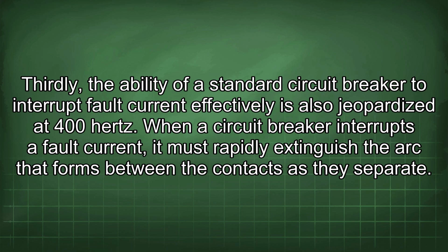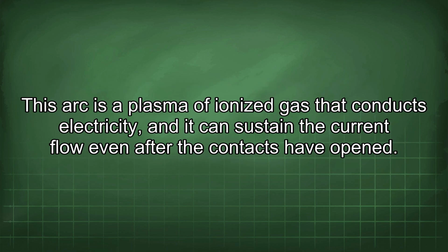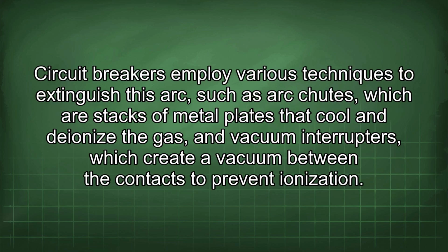When a circuit breaker interrupts a fault current, it must rapidly extinguish the arc that forms between the contacts as they separate. This arc is a plasma of ionized gas that conducts electricity, and it can sustain the current flow even after the contacts have opened. Circuit breakers employ various techniques to extinguish this arc, such as arc chutes, which are stacks of metal plates that cool and deionize the gas, and vacuum interrupters, which create a vacuum between the contacts to prevent ionization.